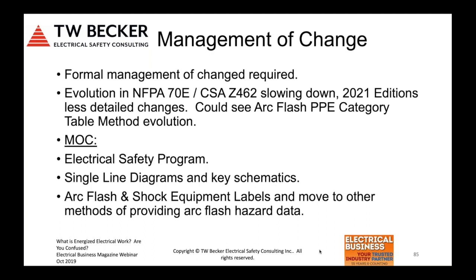So I recommend that we have management of change related to your electrical safety program, and it needs to be reviewed and updated. It should be audited annually, right? And every 3 years, that program needs to be updated based on the changes to the applicable standards. Single line diagrams and key schematics. This is an ongoing challenge. I don't know how we're ever going to get that one solved, but we really need these drawings to be developed, specifically the single line diagrams. Once they're developed, we need them to be maintained.